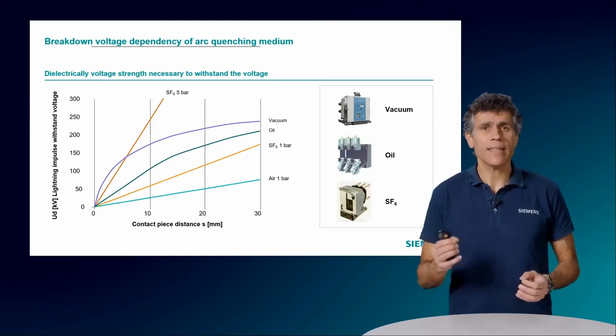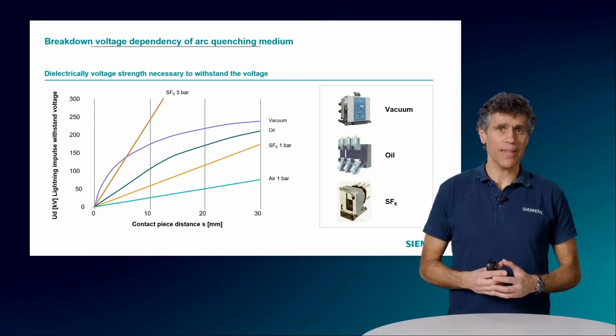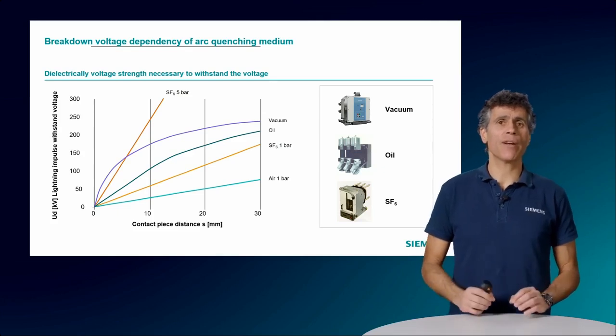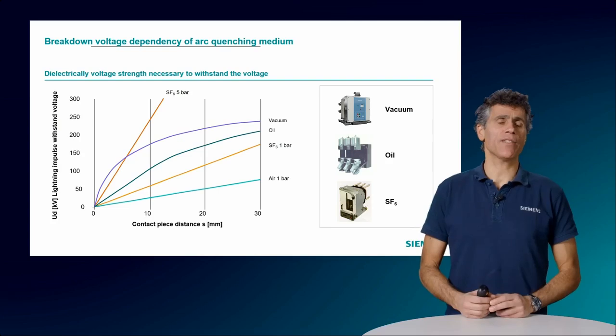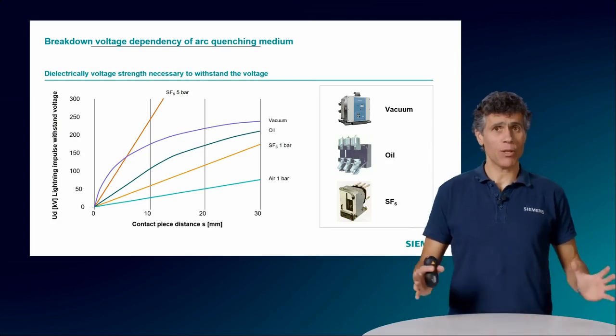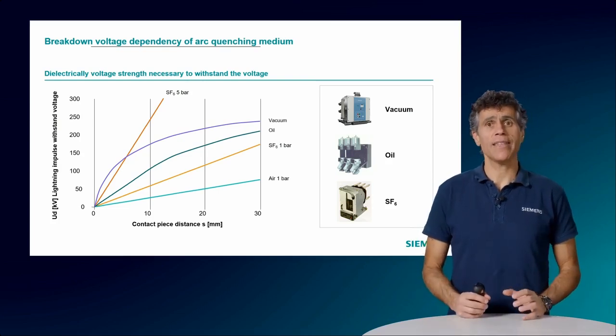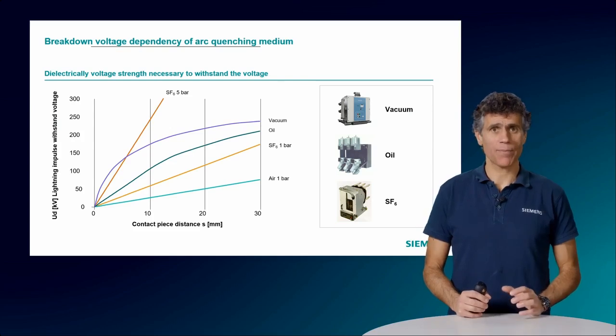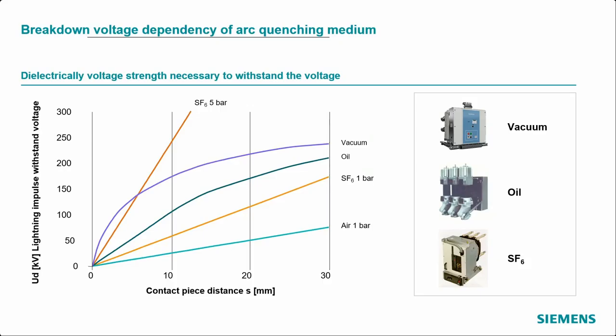So what are the factors behind electrical discharges? Understanding electrical discharges requires insight into two key factors: the spacing between potential charges and the medium occupying that space. With increasing voltage, the necessary spatial separation to prevent a discharge likewise increases. Likewise, when keeping the voltage level, decreasing the distance between the poles increases the danger of rupture. This is what would happen if one would bring both poles closer and closer.